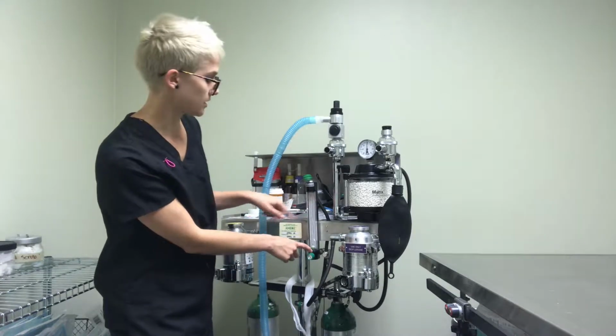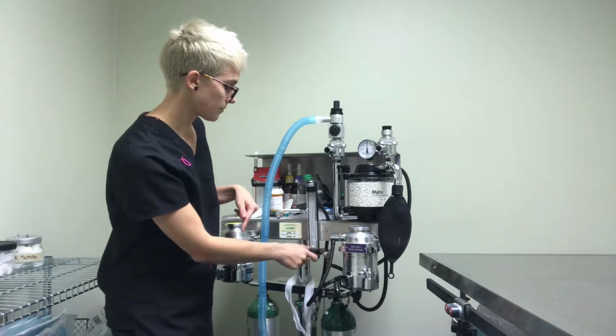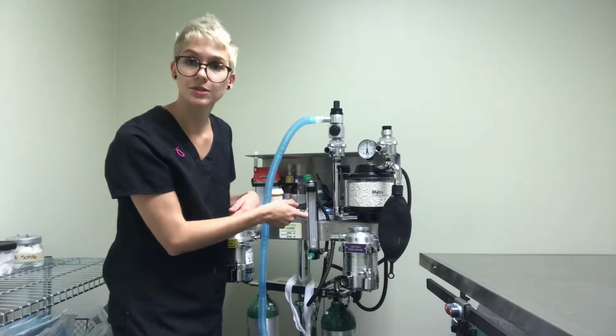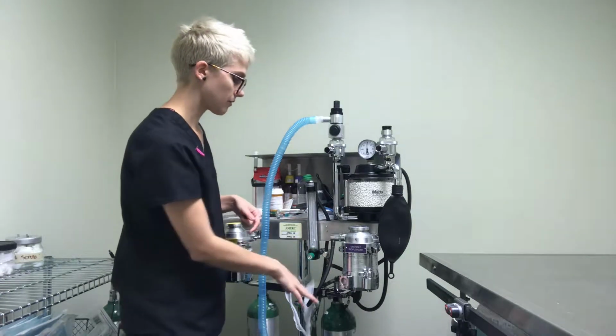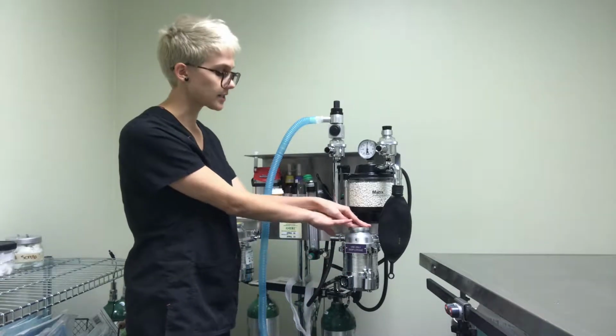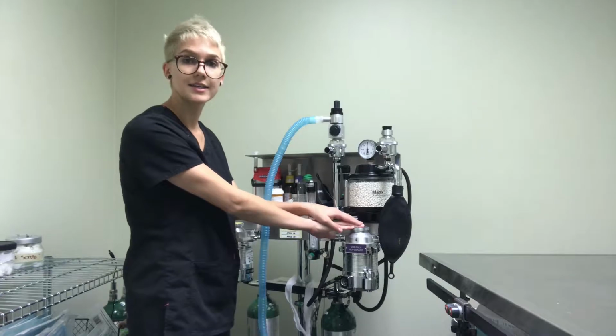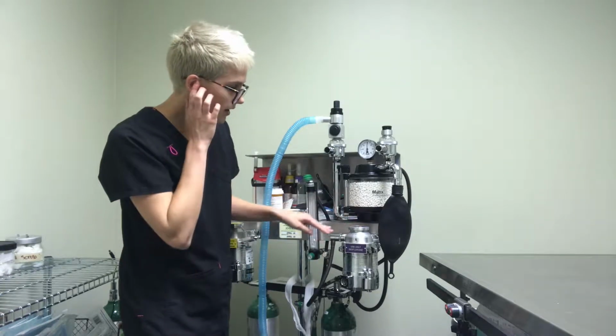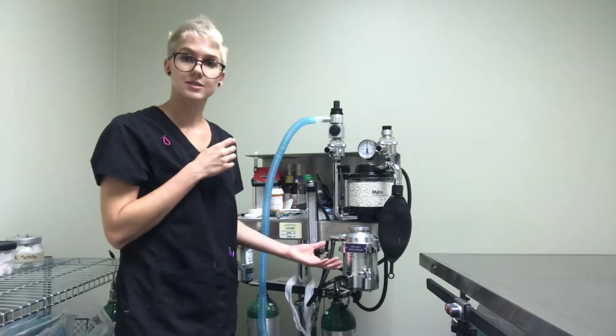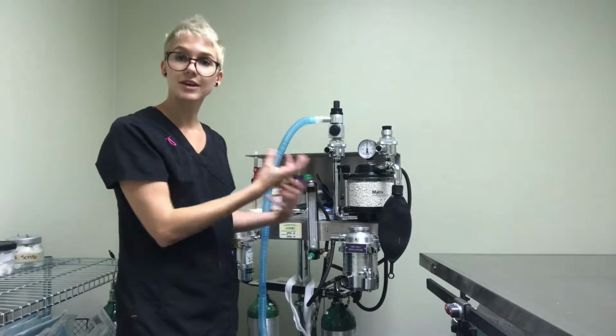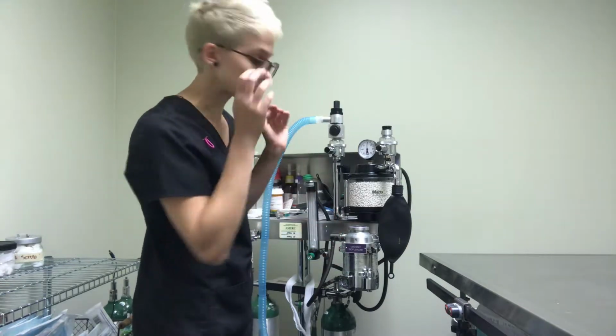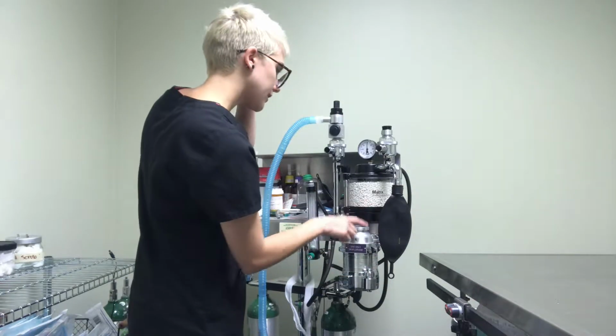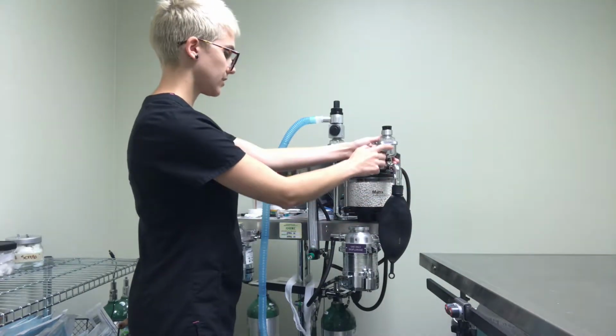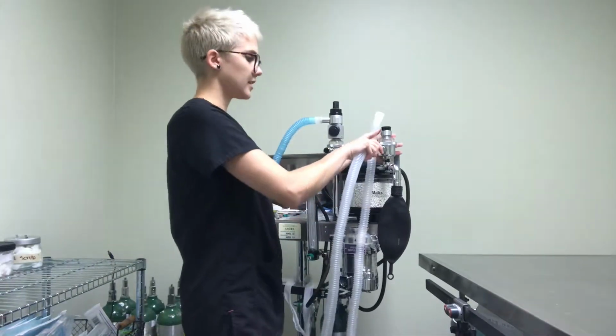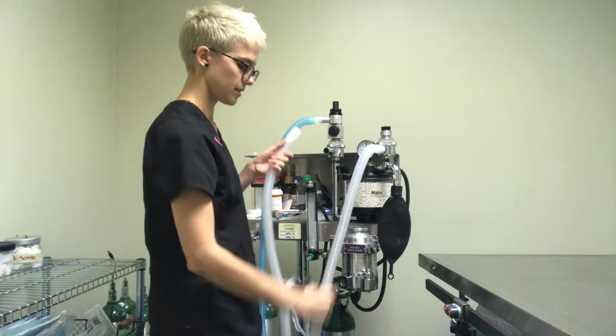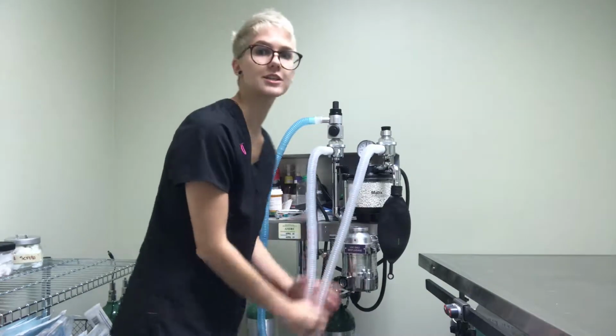This is going to show you, and you can set how much oxygen you want to be flowing into the machine. From there, the oxygen goes into the vaporizer that has the anesthetic gas in it, in this case isoflurane. So this is where the oxygen mixes with the liquid anesthesia, and then it becomes a gas. It vaporizes it. And from there, it goes out the inhalation valve, which is this one right here.